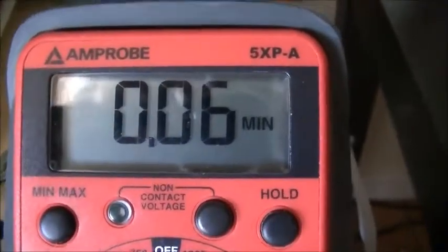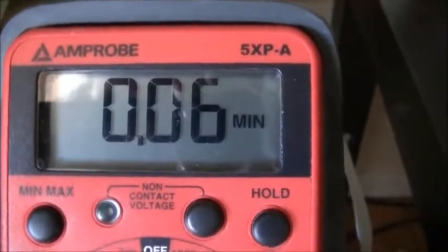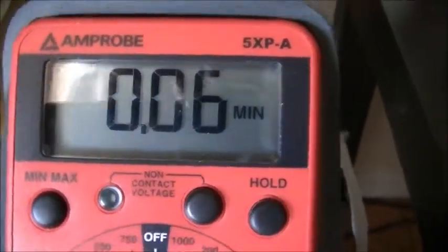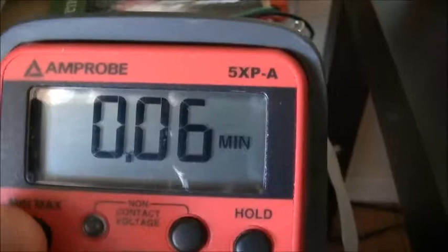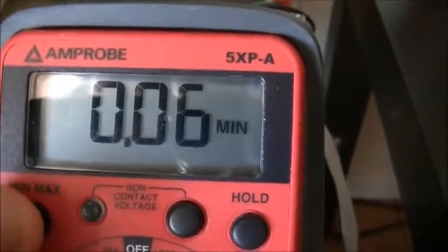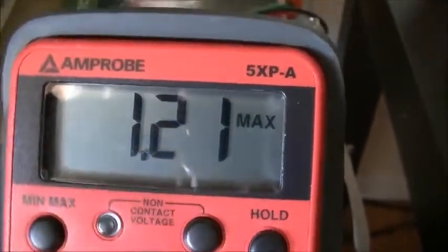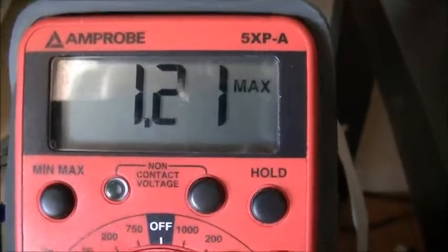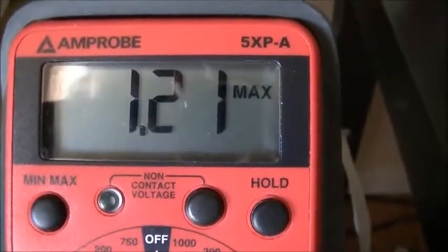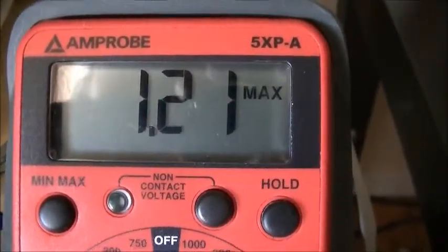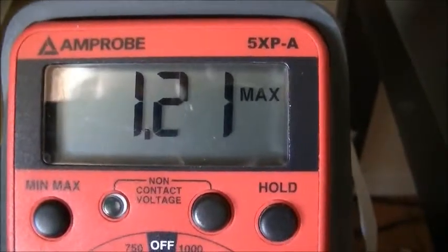This is one of the things with stray voltage: it follows the loads of the electrical system. When you have very low loads overnight, you get very low stray voltage. When you get the high air conditioning loads of the daytime, you get these high voltages on the AC electrical grounding system.